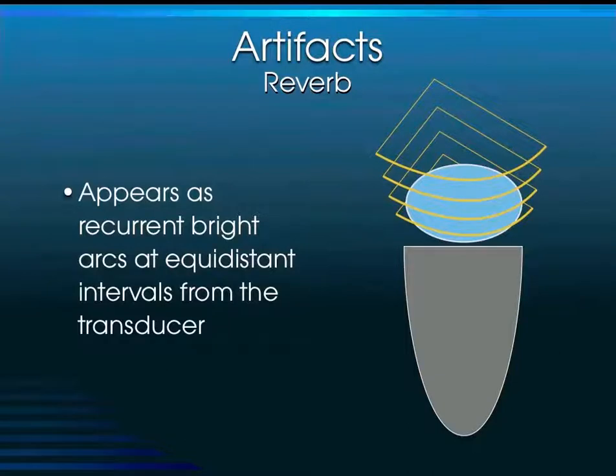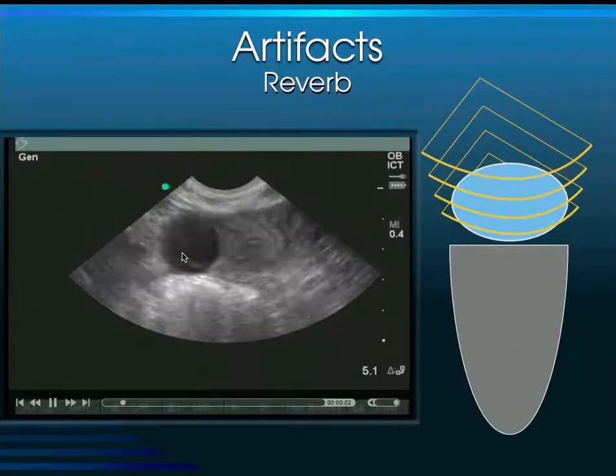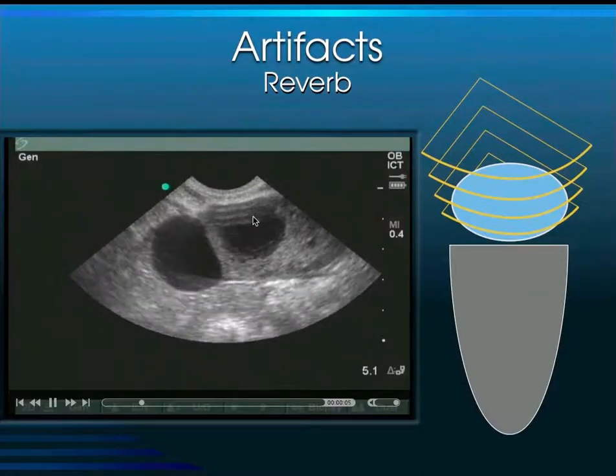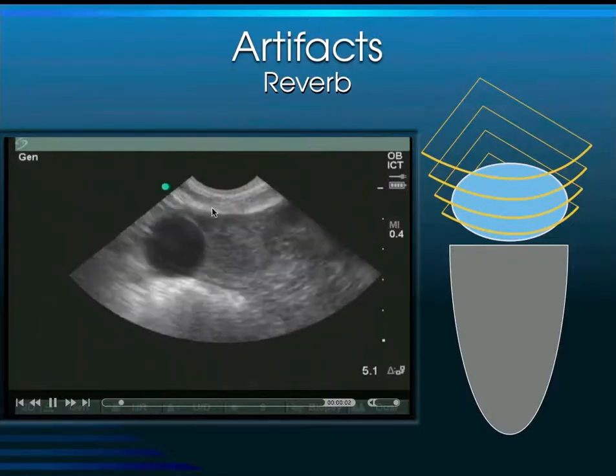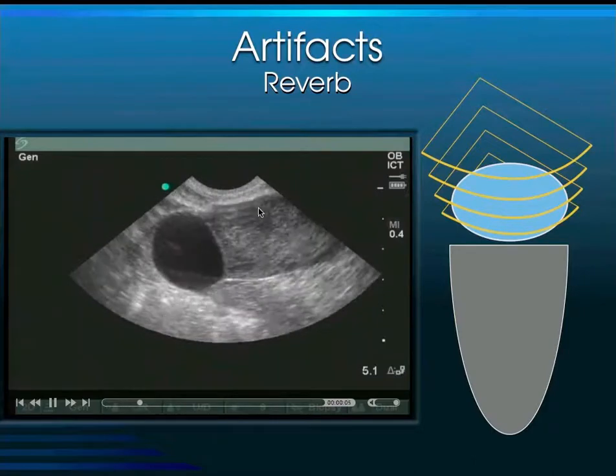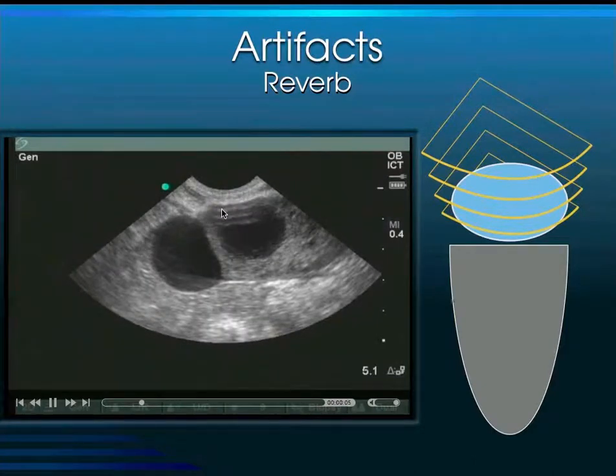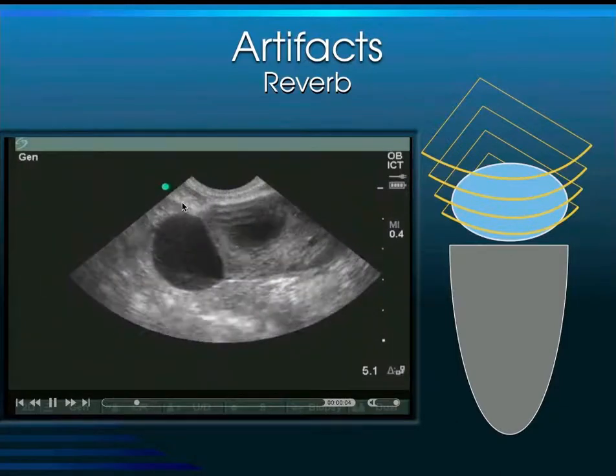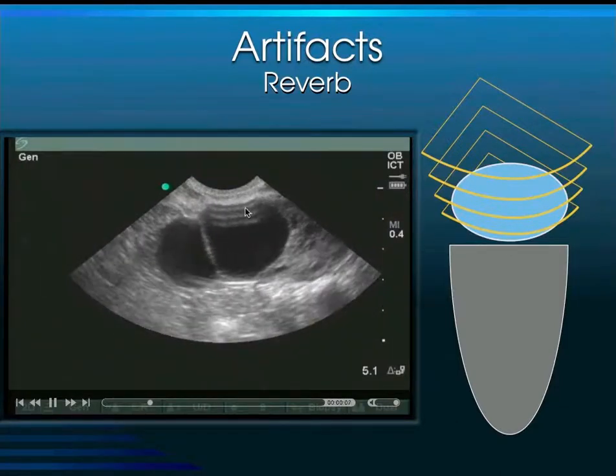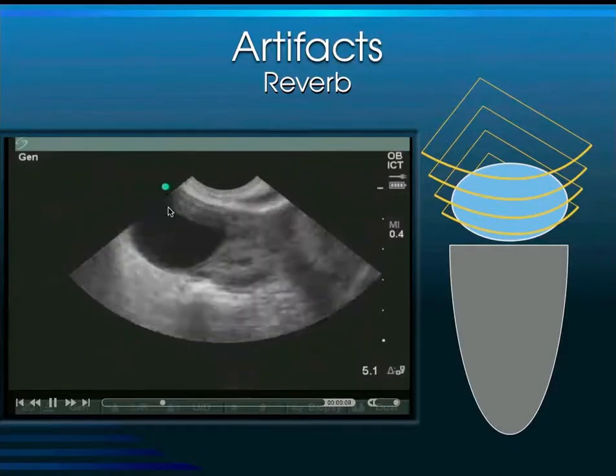Reverberation artifact appears as equidistant arcs from the transducer. When you see these equidistant reverberation artifacts — common with curved or phased array transducers — you don't want to mistake them for something anatomic or pathologic. For example, in an ovarian cystic structure, equidistant arcs visible on screen are simply reverberation artifact, not a clinical finding.